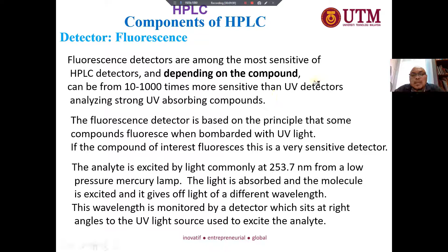Okay, let's look at the advantages and disadvantages of fluorescence. On the advantage side, fluorescence HPLC measures a specific property, which means the compound needs to be fluorescent. So it is specific, and it can neglect anything that is not fluorescent, so it neglects interference as much as possible. That is the advantage. But of course, the disadvantage is that it detects fewer compounds. It can only detect fluorescent compounds. That's why fluorescence is not universal, with limited application to particular fluorescent compounds. But when it measures the specific property, it enhances that particular detection, so it can increase the sensitivity. So it is highly selective as well.